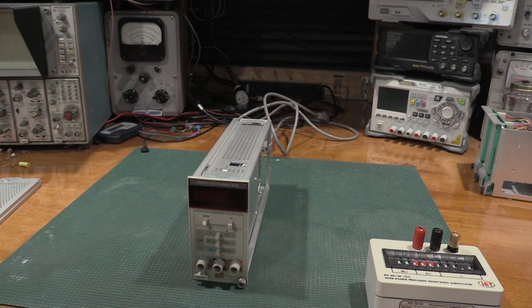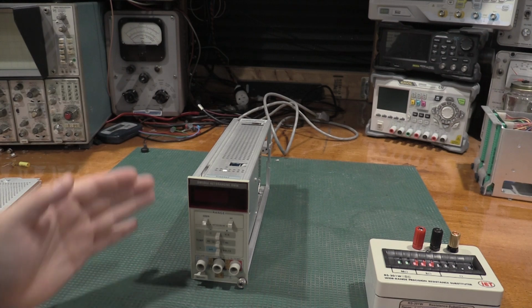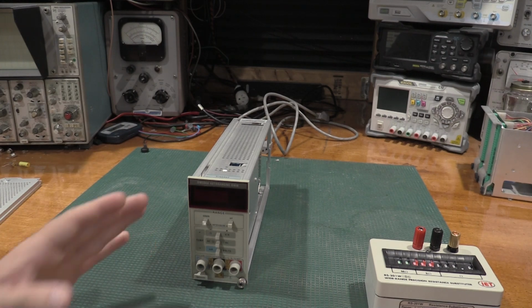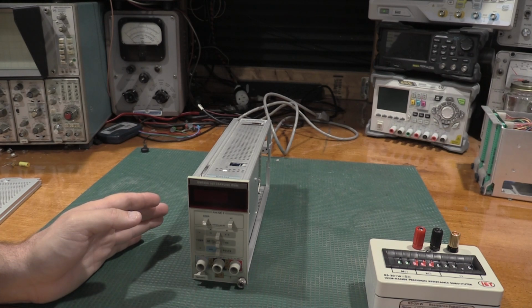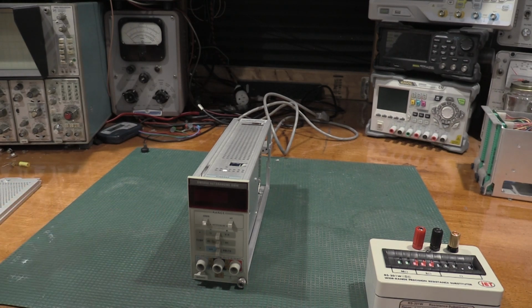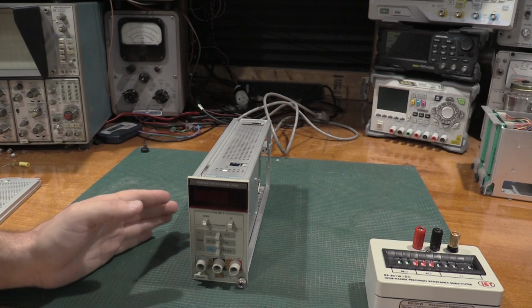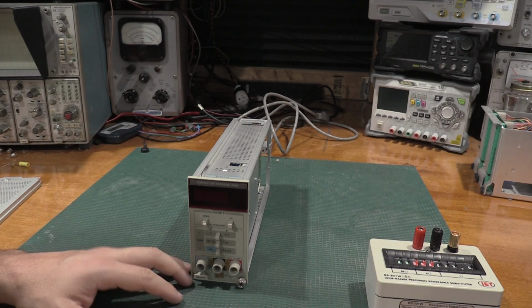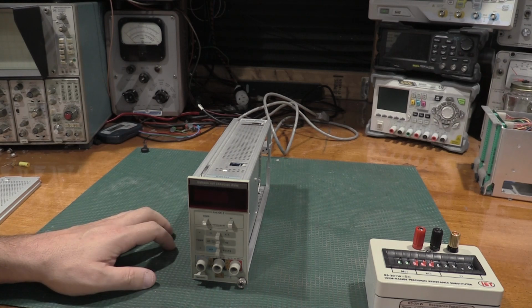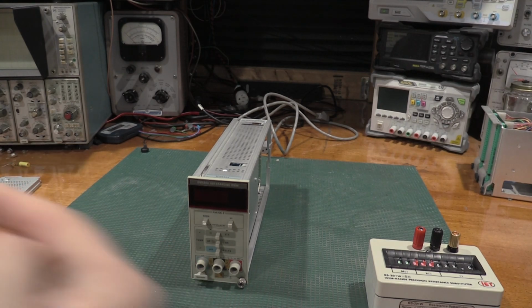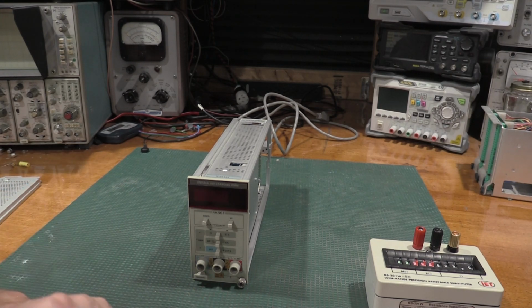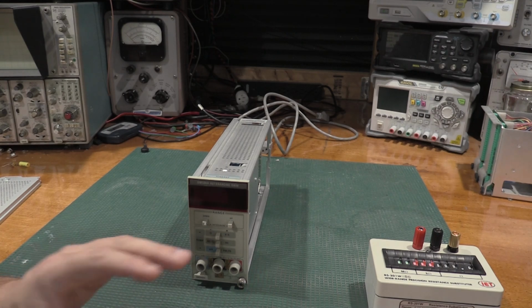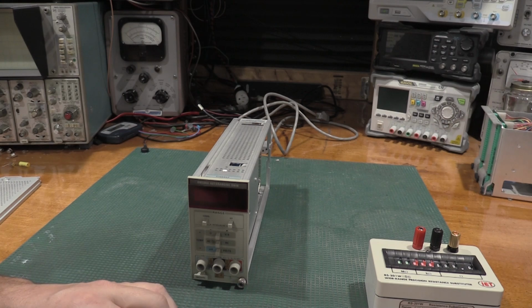So yeah, when I send the 7510 out to get aligned and calibrated, well, I don't send it out to get aligned, I send it out to be calibrated. They check it, it says, yep, everything's within tolerance and spec, and they send it back with a report that says this is what it actually measured. So the nice thing is, as you get those reports, you can watch how the unit's drifting back and forth, because as this stuff ages, it will move around a little bit. Some of the Keithley gear and some HP gear, especially some of the HP gear we've worked on in previous videos, these function generators and stuff that are behind me, they have some incredibly tight tolerances, so dialing those in can be a job.